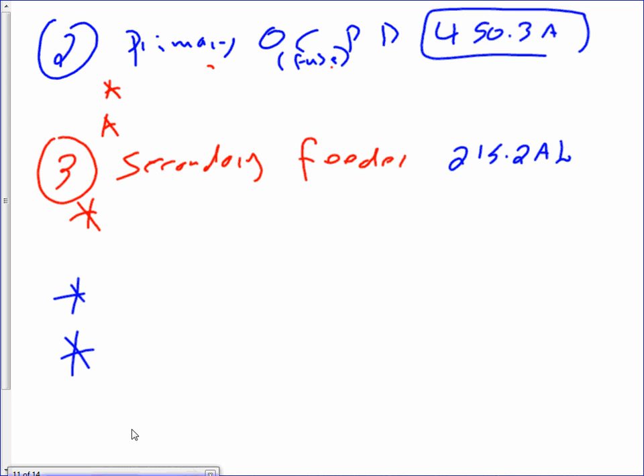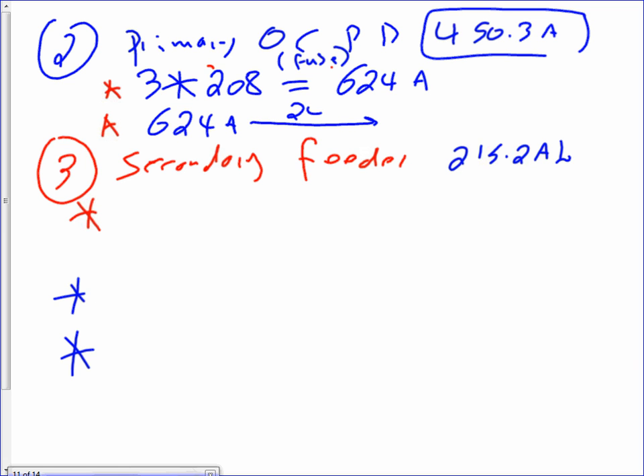Okay. Now, armed with this information, let's go to the next standard. So, I'm going to multiply by 3. Anybody know why 3? The fuse. 208 multiplied by 3, the full load current of that motor, gives me 624 amps. Since they don't make a 624 amp fuse, I have to go to 240.6. Gentlemen, you are dealing with a 700 amp. You can go up to 700 amp. Do you have to go up to 700 amp? No. On the test, what should you do? You have to go with me on the test to the next standard size up. In real life, it's up to you. You can still go down if you want to. Going up is an option, not a must, in the code.